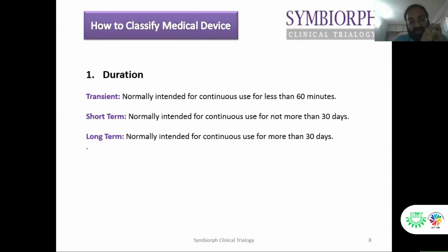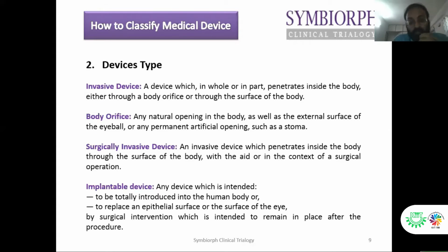After you have classified your device as per the duration, the next thing is the device type. You have to define which category of type the device you intend to manufacture, or to make a proof of concept for, falls under: whether it is an invasive device, a body orifice device, a surgically invasive device, or an implantable device. I will start with the invasive device: a device which in whole or in part penetrates inside the body, either through a body orifice or through the surface of the body. You can classify it as an invasive device. We will see examples and case studies at the end of the classification. I have taken around four to five case studies to show you how to classify further.